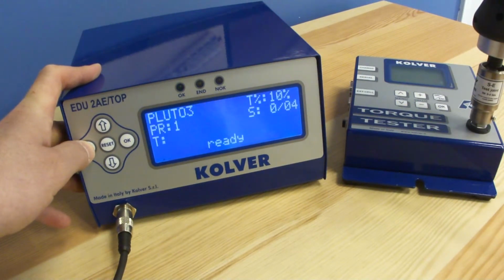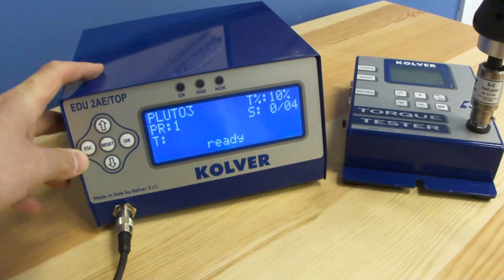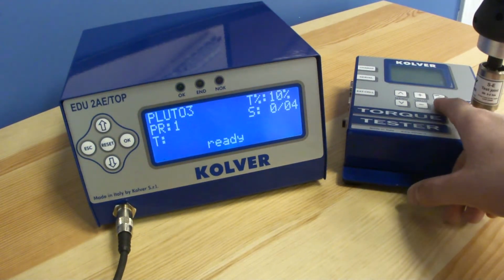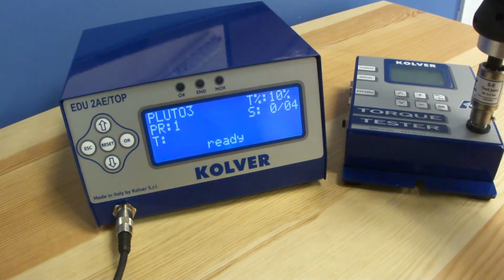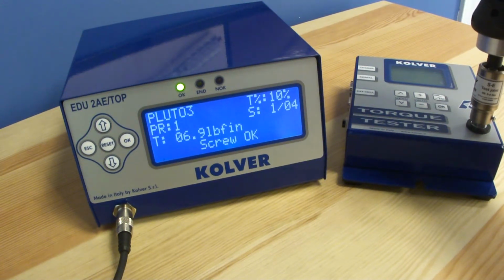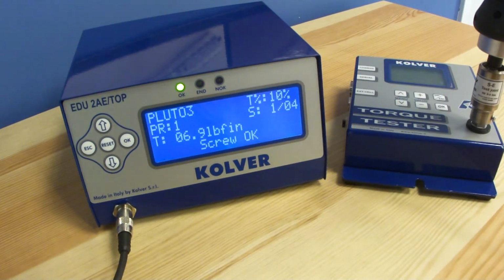I then exit to the main menu, where now I should be able to perform a series of rundowns on my calibrated torque tester and see a representation of the results on the screen of my EDU2AE top. What I'm seeing on my torque tester is 6.9 inch-pounds, and I'm also seeing 6.9 inch-pounds on the screen of the EDU2AE top, letting me know that I correctly have done the calibration procedure.